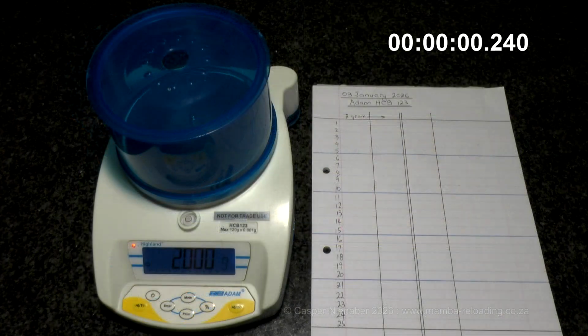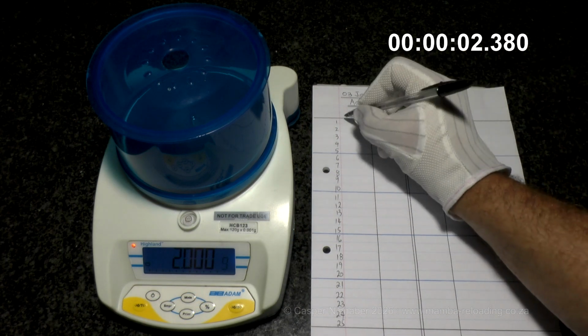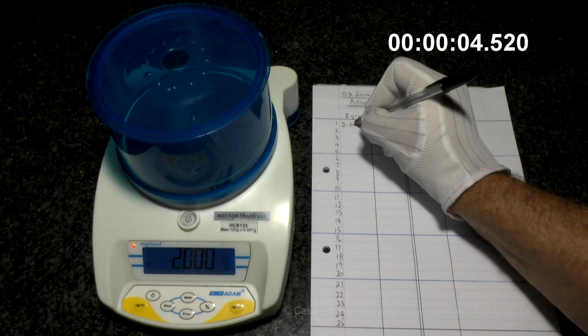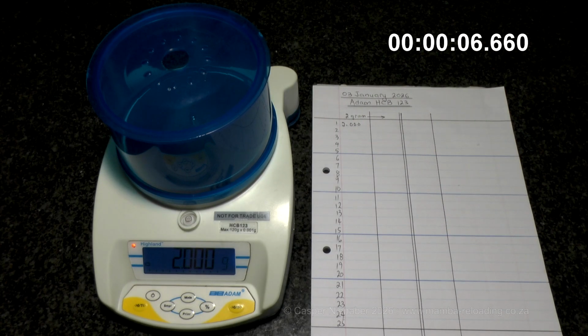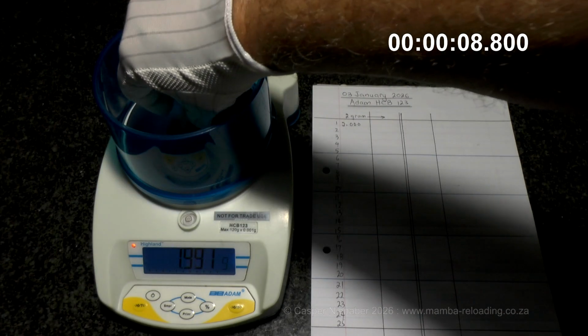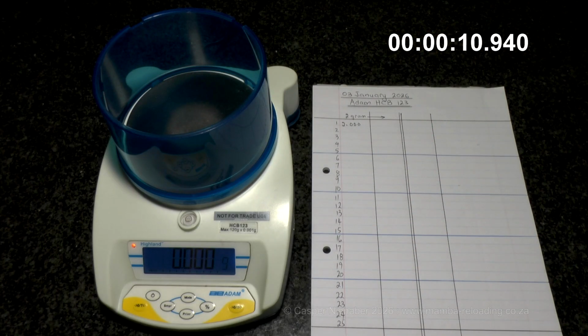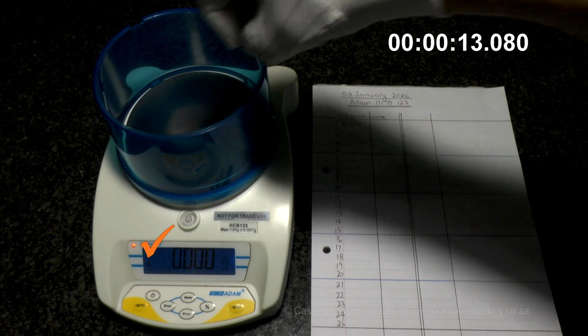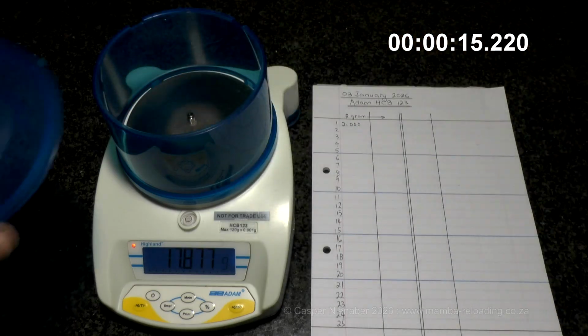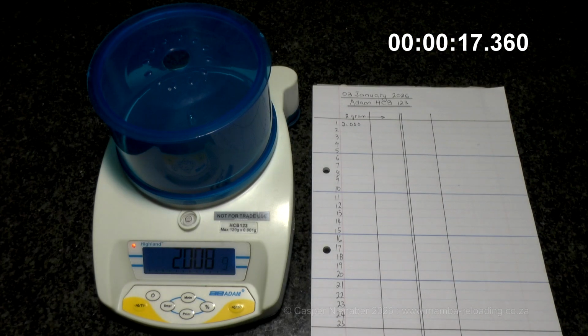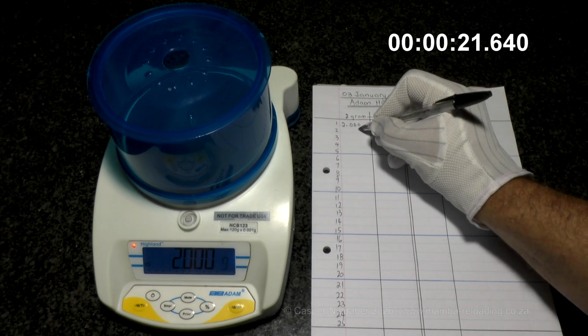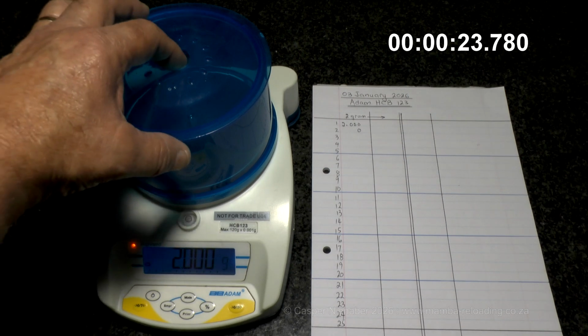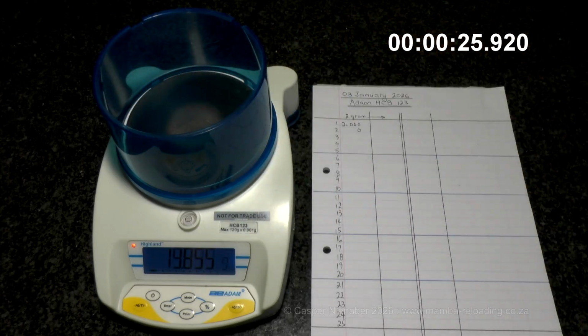I will now weigh and record the same 2 gram test weight 50 times to the nearest milligram. After each weighing, I will remove the weight, wait for the balance to stabilize and return to 0, then replace the weight and close the draft shield. I will show the full process for the first 10 readings only. After that, to save time, I will show only the stabilized readings.